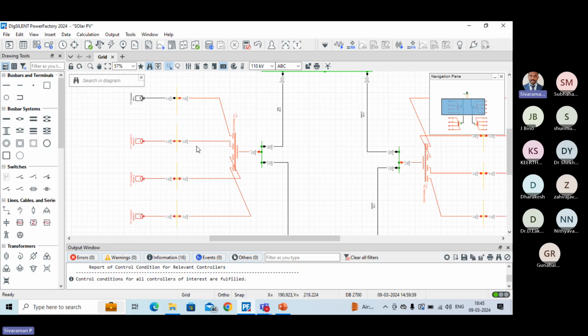Okay, so I think we have come to the end of this presentation. I will summarize it. I covered the design aspects of a 50 megawatt solar PV plant, considering the inverter and the layout based on the useful land availability. To design the solar PV plant, the first step is to arrive at the inverter block capacity. In this example, 50 divided by 4, that is 4 inverter blocks, so 12.5 megawatt is the individual inverter block capacity.